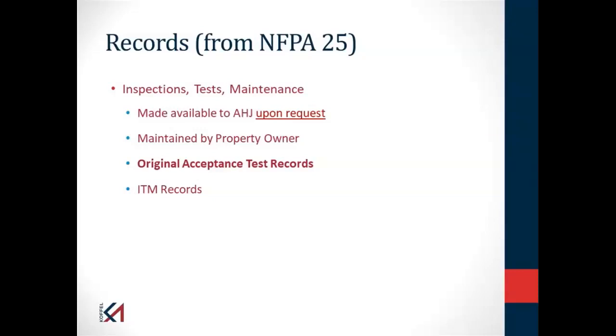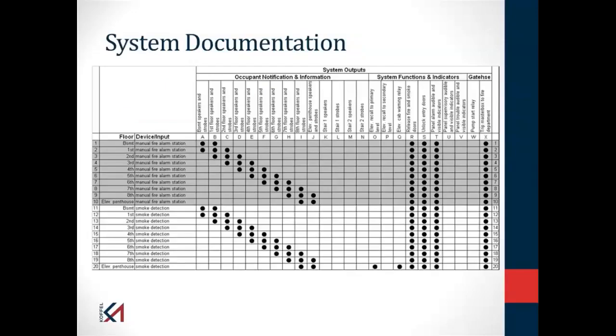I had a water leak in a hospital and was representing the sprinkler contractor. A coupling failed, and they could not produce proof that they had done the hydrostatic test when the system was installed. That doesn't necessarily get them off the hook, but it helps in my defense to say the system withstood 200 PSI during the acceptance test. As it stood, we couldn't verify an acceptance test had ever been done, so they're now more at risk for not having that documentation. And you as an owner are required to do it.